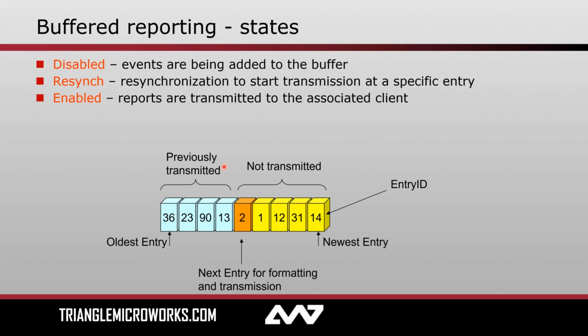So a little bit more about buffering. There's really just a few possible states that a buffered report control block can be in. First, it could be disabled, in which case it's just sitting there accumulating reports. As data changes that's contained in its data set, it stores that information in a buffer, with an entry ID indicating what that data is and when it occurred. During the resynchronization phase, this is when a client is actually establishing that connection, maybe for the first time or maybe after an interrupt. In either case, that's when the data is being flushed out of the buffer and sent up in a serial way up to the client.